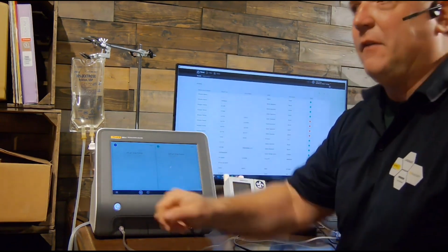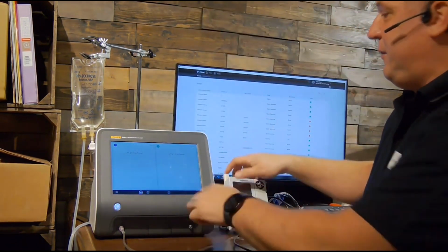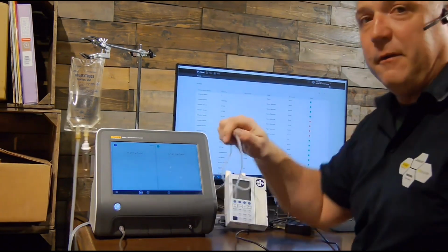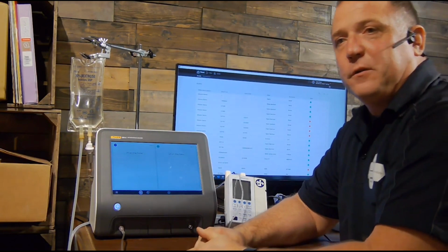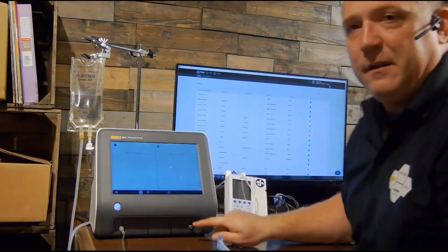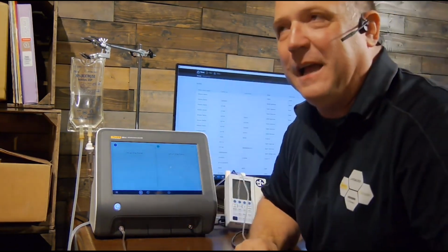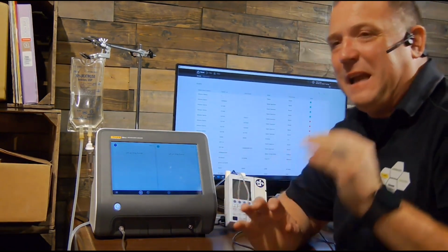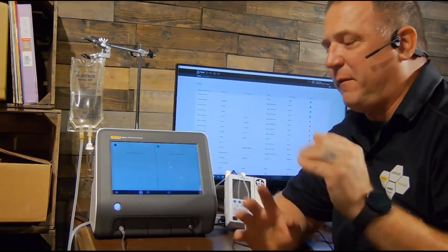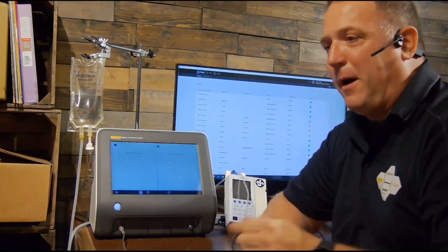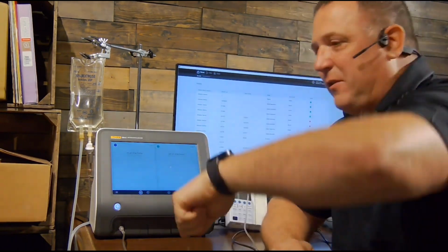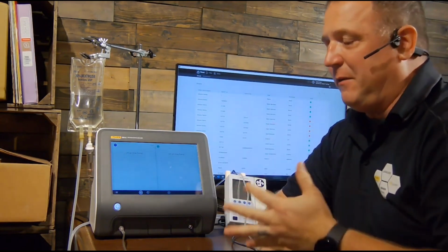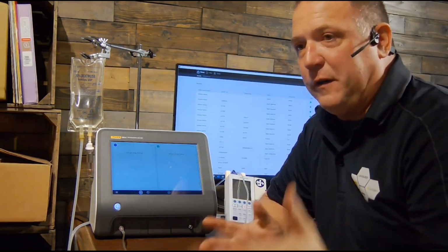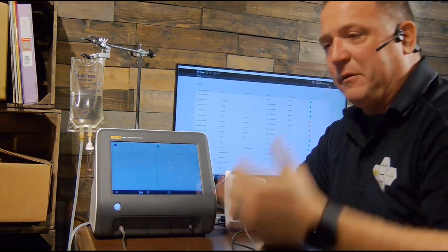And when I'm going through all the procedures, the only thing I did is change out my tubing. I grabbed the set for flow, put it into my infusion pump, and did my flow test. When it was time for occlusion, I took that set out, plugged in the occlusion set, and ran my occlusion test. Even there, we were saving a lot of time. I want to say like 3 to 5 minutes per pump because we didn't have to change all around. We didn't have to dump the cylinders. We didn't have to dry the cylinder. We didn't have to tare out the scale. And again, those scales aren't transportable, because if you move the scale, you have to re-zero it. So we actually saved a lot of time.